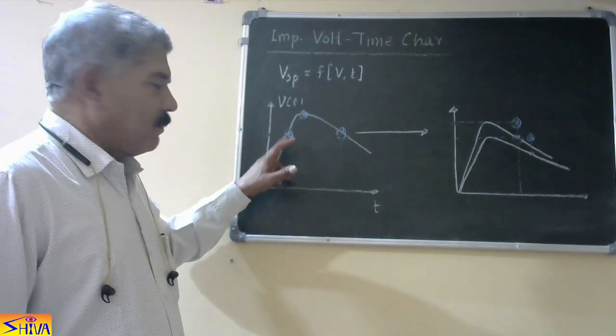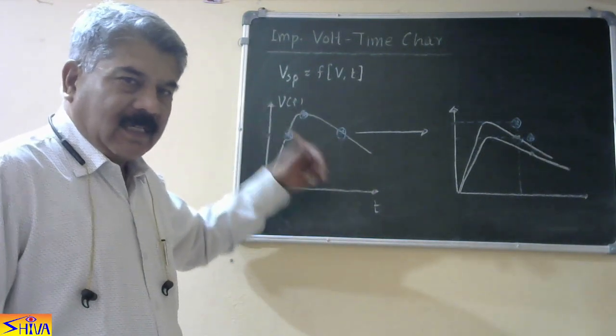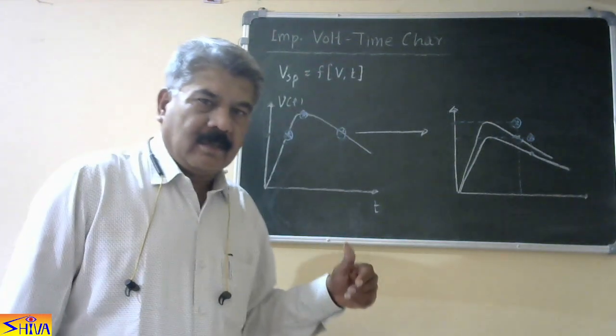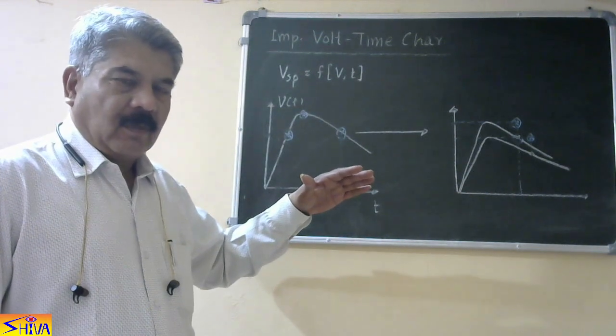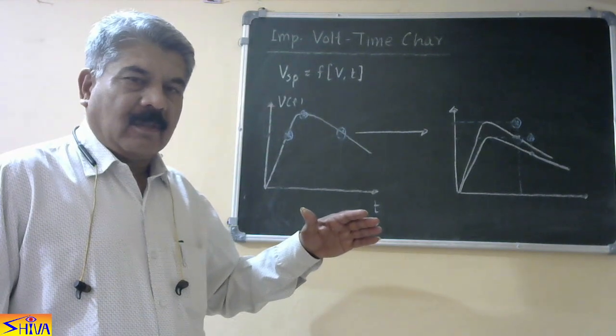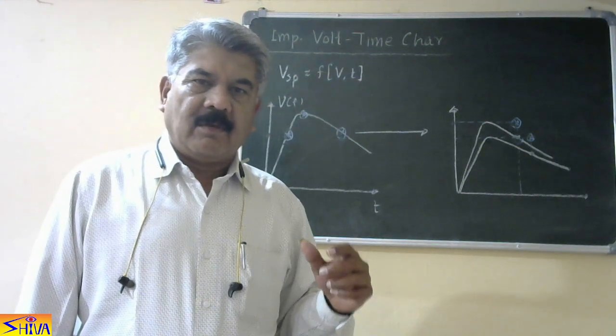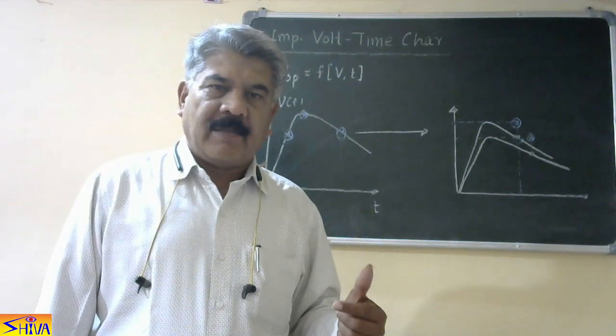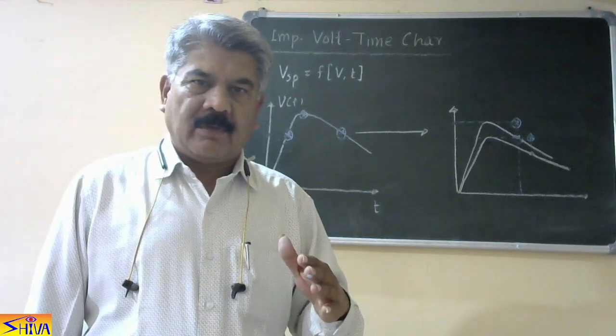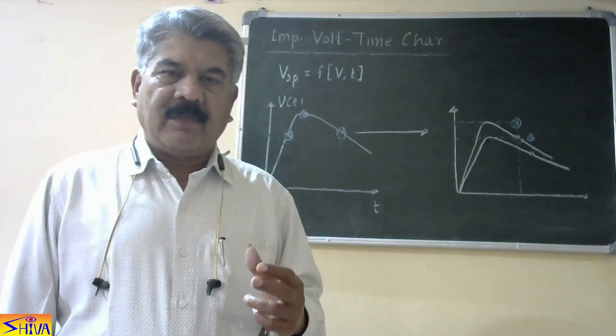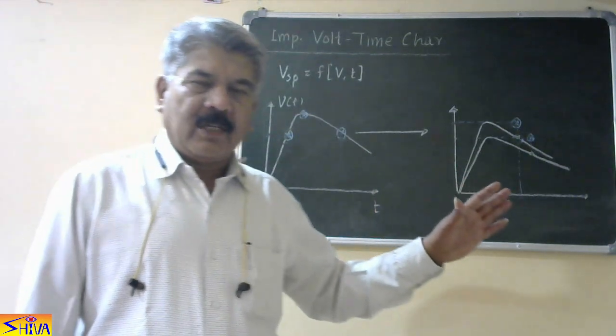Remember: if spark over takes place at the rising portion, in the next consecutive attempt we reduce the amplitude of the impulse wave so that the insulation sustains the voltage for a comparatively longer time. Then we find the point. Again we apply the voltage but with reduced magnitude so that the time for which it can sustain the voltage is different. Finally, we join all these points by a smooth curve.